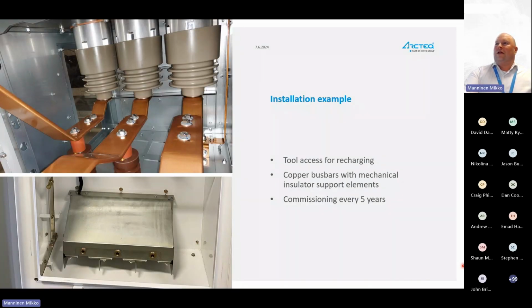Here's an installation example. This is a medium voltage one. It is wired and bolted to the main bus bars. Commissioning is recommended every 5 years, and not all of them can be commissioned. So there are differences, but there are some units which can be commissioned, and they are always the ones which can be reused. If it is possible to commission, then it's every 5 years or during the maintenance program your site already has. So if your site maintenance and recommissioning program is 3 years, then you should use that.